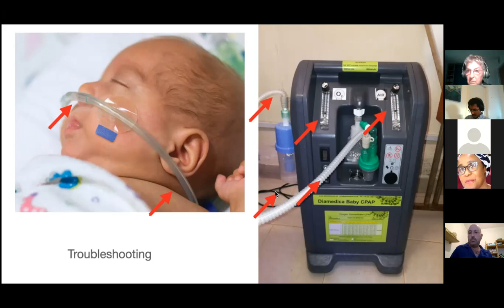if we provided enough pressure, so at least 5 centimeters of water. And we check the flow gauges to see that there is enough flow. As we said, combined should be 10 liters per minute, and that there are bubbles in the humidifier tank and also on the CPAP tank. And another thing, of course, we need to check if there is any problem with the electricity, because there is sometimes some problems with the surge in the units.